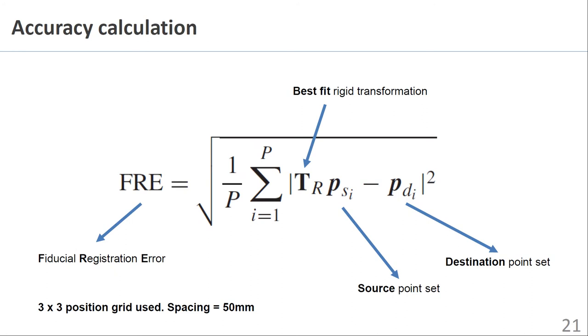Accuracy results were derived using the fiducial registration error, a root-mean-square error approach that measures how well a spatially distributed set of points aligns with an ideal set of corresponding points. In this work, a 3x3 grid of locations on the polycarbonate test board shown previously was used. The error is calculated as the RMS difference between the locations of the ideal grid and the corresponding locations as reported by the magnetic sensor, following a best-fit transformation, capital T.